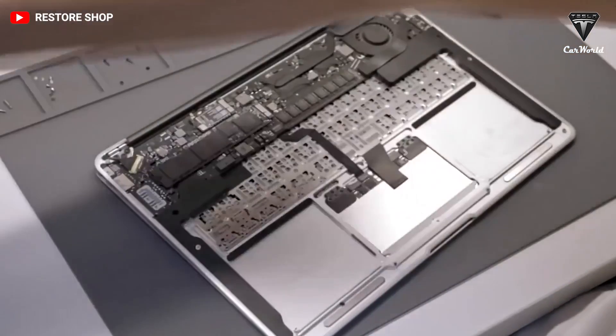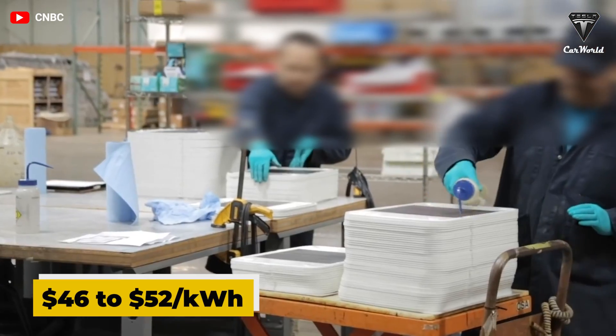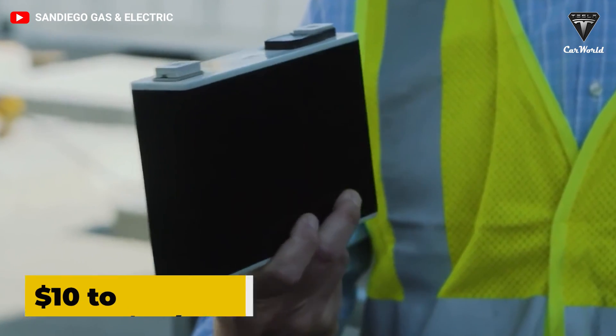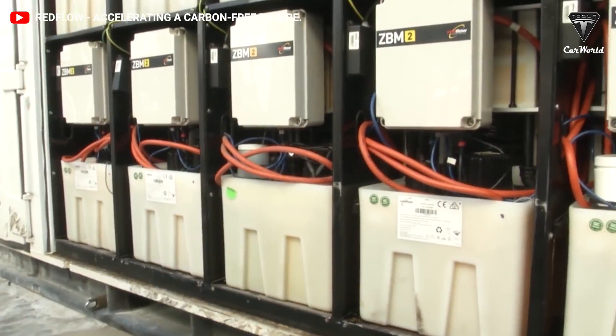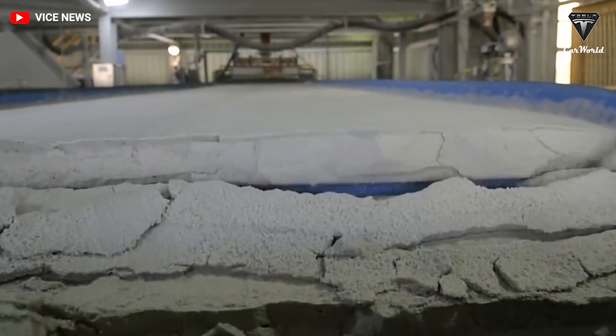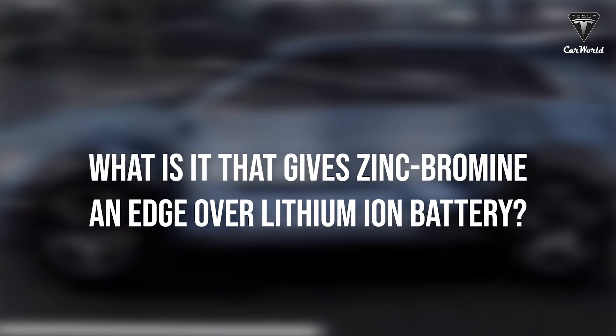For the cost of systems integration — which involves shipping and installing the batteries — Department of Energy figures for lithium range between about $46 to $52 per kilowatt hour. The cost for zinc bromine is between $10 to $18 per kilowatt hour. In other aspects like engineering, construction, equipment, connecting to the grid, and transformers, zinc bromine is also cheaper.